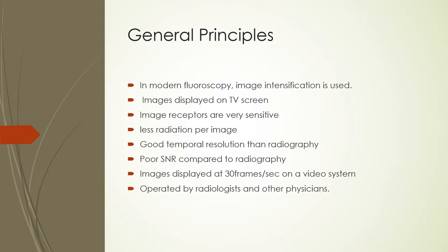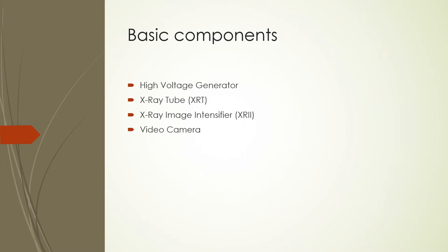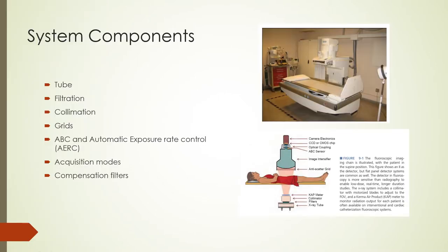In many situations, fluoroscopy is operated by the radiologist, so it is important for radiologists to know how the system operates, what factors influence patient dose, and ways to minimize exposure to patient and staff. Basic components of a fluoroscopy system include a high voltage generator or power supply, an x-ray tube, and an x-ray image receptor which also intensifies the image at the video camera. On the next slide, we shall start with the x-ray tube.